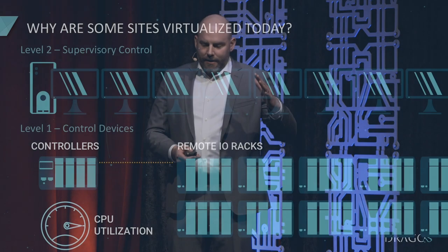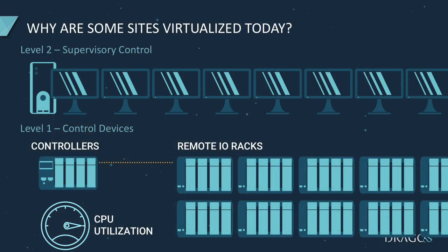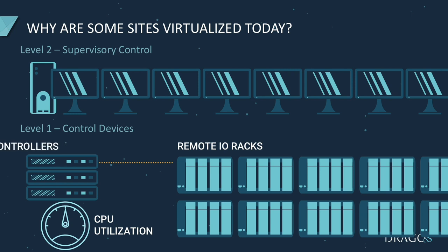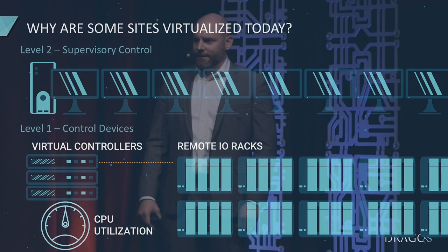So what we're seeing across a number of different DCS vendors is the virtualization of these controllers. When they hit that peak, they will add in commodity IT hardware and use that as the processing CPU for these control systems rather than the traditional industrially hardened CPUs. This works well in DCS environments because those servers are often in climate-controlled areas of the plant anyway, so they don't need to be overly industrialized.